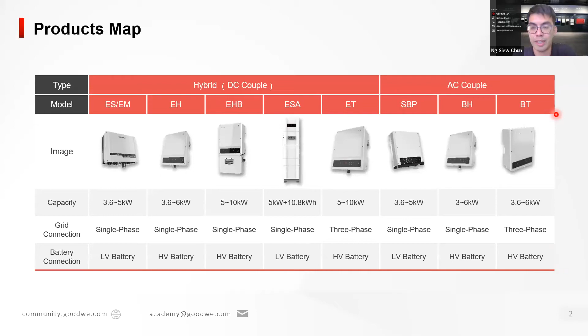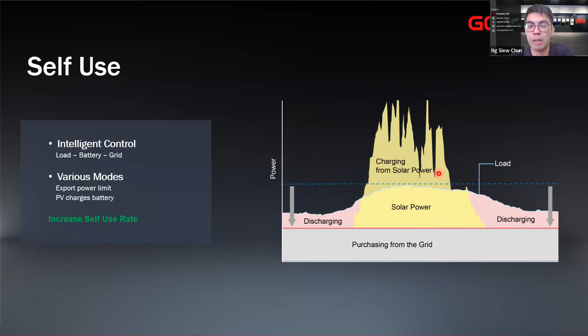The first operation mode is maximizing self-consumption. This is basically the load consumption curve of a residential home. During the daytime there is excess power from the solar generator, so we use that excess power to charge the battery. During the evening or early morning period, the battery can discharge the stored power to maximize self-consumption. All of this solar power is used for local consumption without any export to the grid. This increases the self-consumption rate of a household.